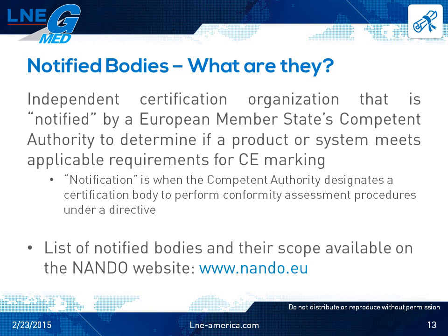So, for LNE-GMED, the French competent authority, ANSM, has designated us, or notified us, to perform conformity assessments for medical devices. I should note that even though we're just designated by the French competent authority, we're able to perform conformity assessments for the entire EU, like all notified bodies. Once we're recognized by one competent authority, we're recognized by all of them. There is no notified body that is designated or notified by more than one competent authority.